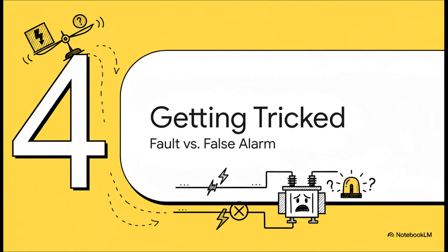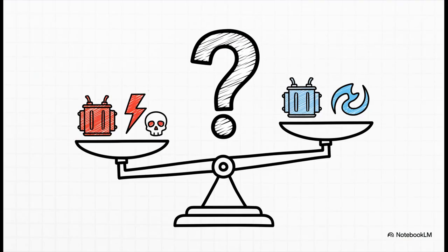But, just like any security system, there are ways to trick it. This simple, elegant principle of balance, well, it isn't always enough. Because sometimes the transformer itself is the one creating a false alarm. And this is where it gets really clever. Let's go back to that security analogy for a second. What if the building itself, for some reason, could just generate a harmless clone of a person that never leaves? The security system would go nuts. This is the challenge. Not every imbalance is a real destructive fault. Sometimes the transformer's normal operation creates an imbalance that's totally safe.